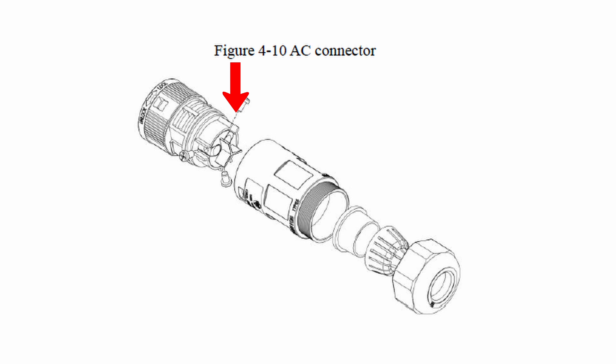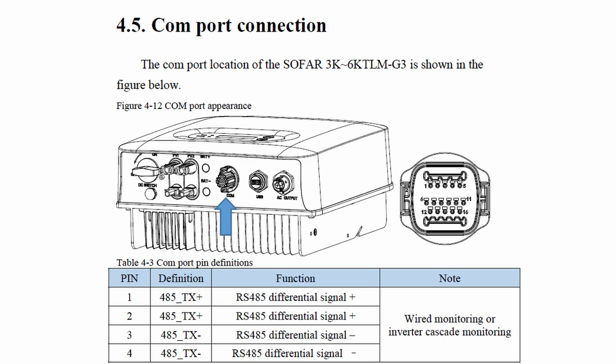COM port connection is crucial. Many have issues not being sure which one to use. Pins 1 to 4 are to connect inverters in cascade mode. Pins 1 and 3 are input, pins 2 and 4 are output. From the first inverter, connect pins 2 and 4 to pins 1 and 3 on the second inverter, and so on until the last one. The last one should be closed on the communication between pins 1 and 3 with a 120 ohms resistor.